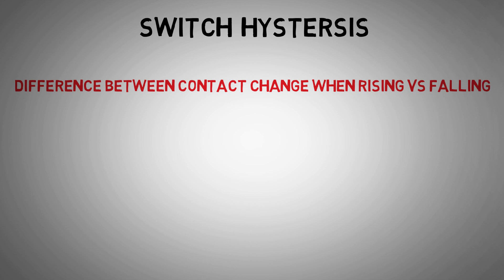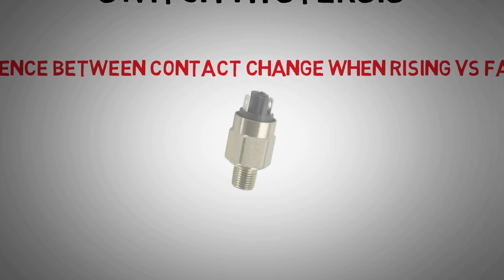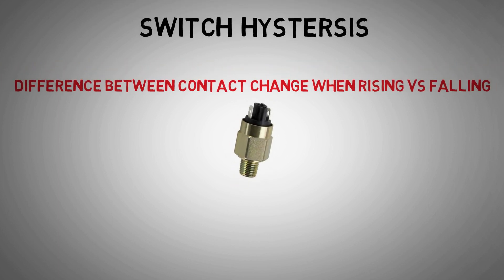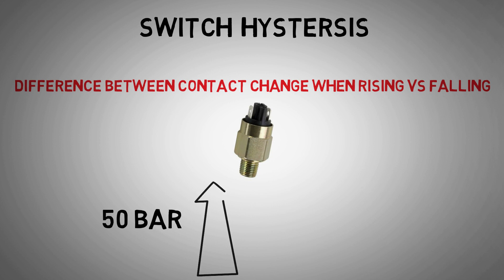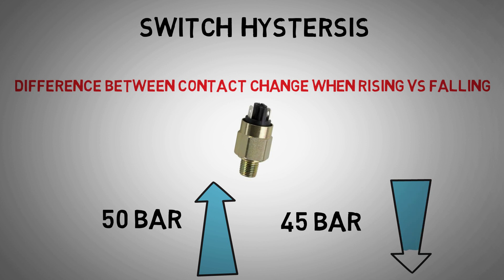In our pressure switch example, we could have it set up to 50 bar rising, where any pressure higher than 50 bar will change the state of the switch. The switch may not go back to its original state until the pressure is, say, 45 bar falling. This is what we call hysteresis.